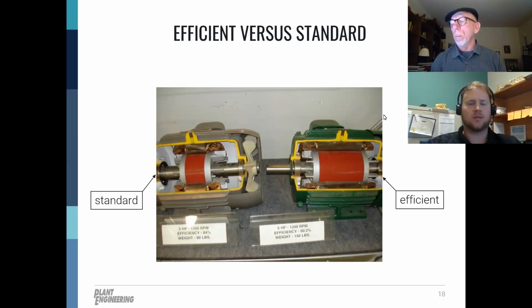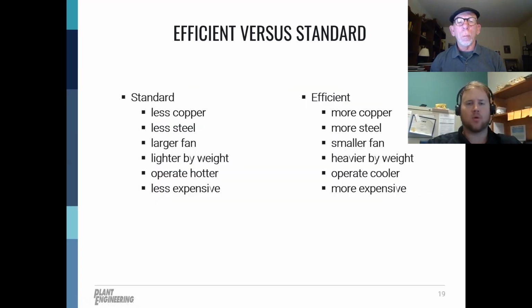Generally speaking, an efficient motor would have more copper and more steel and a smaller fan than its less efficient counterpart. The increase in steel and copper makes the motor heavier, of course, by weight. And we all know more material means more money. So a higher efficiency motor will likely be more expensive.